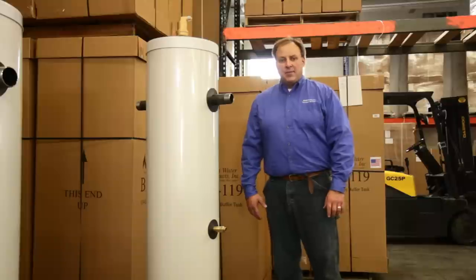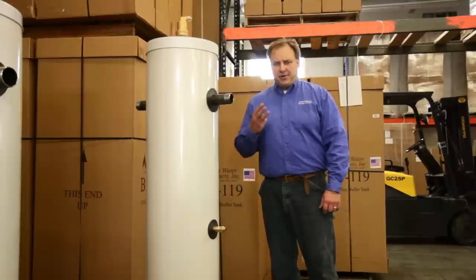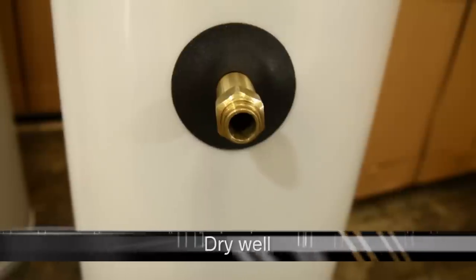Beyond that, servicing a wet well can be a nightmare because it inevitably requires draining the tank. And draining the tank means you have to refill the tank, which, unless you have a boiler buddy, can be a hassle in and of itself. The best way to gauge your tank's temperature is method number three: installing not a wet well, but a dry well. With a dry well, you get the same accurate readings as a wet well, but with the threat of electrolysis completely removed, because the sensor sits inside a sealed sleeve or well that extends into the tank.